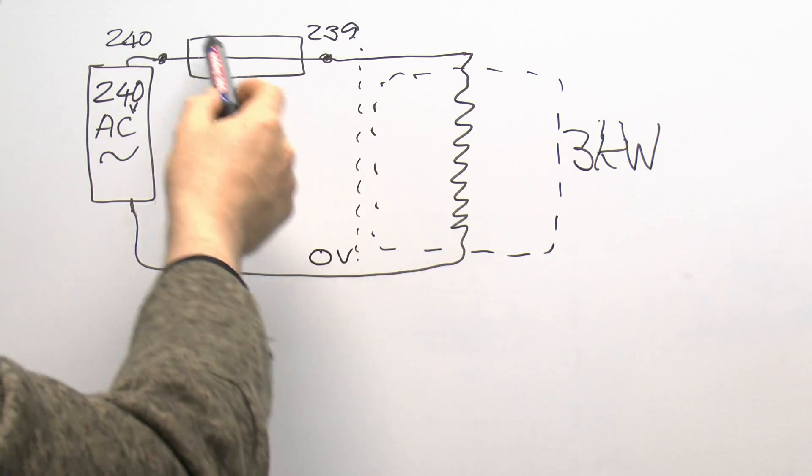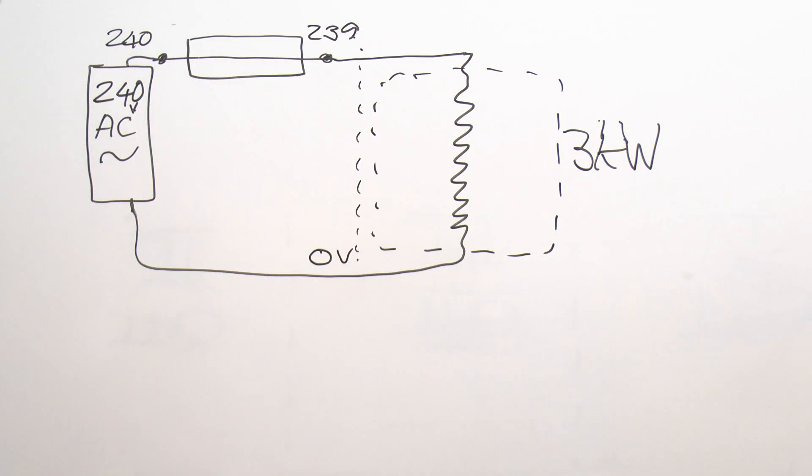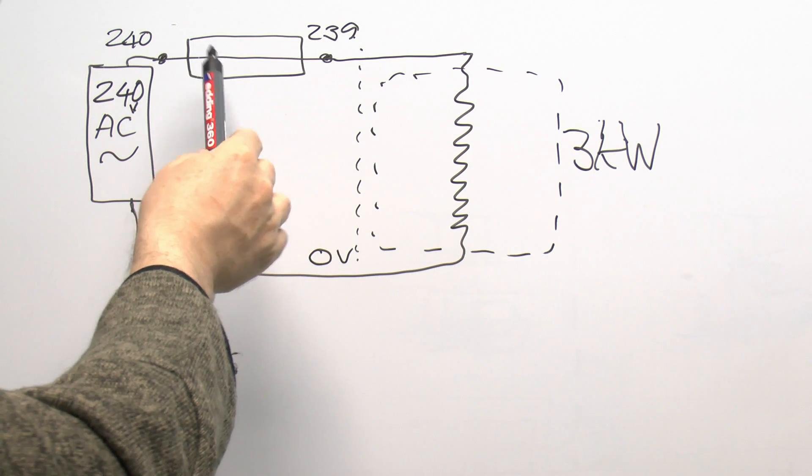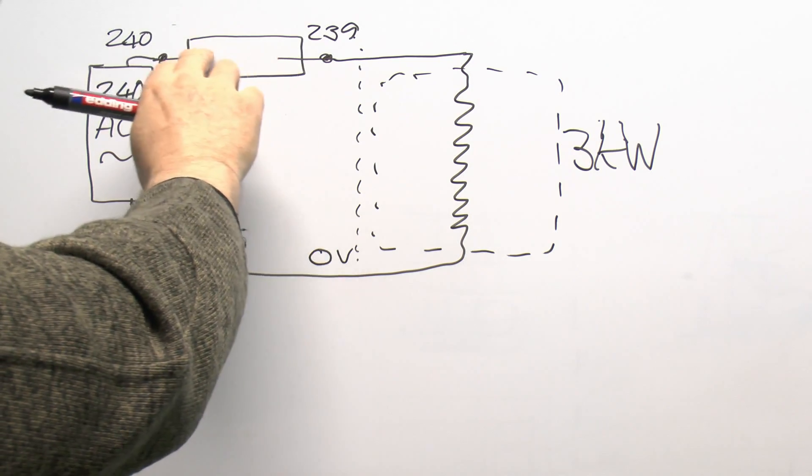So the vast majority of the voltage is going to be across these two points with only say one volt or less across the resistance of the fuse element. Now one major difference with this compared to the direct test with just a couple of volts across is when the fuse actually fails.